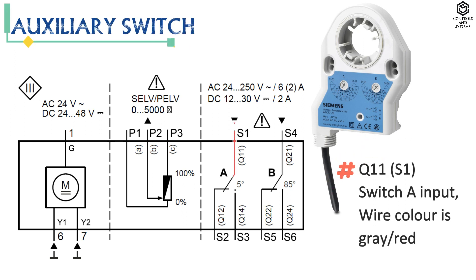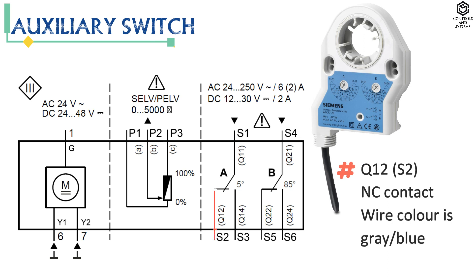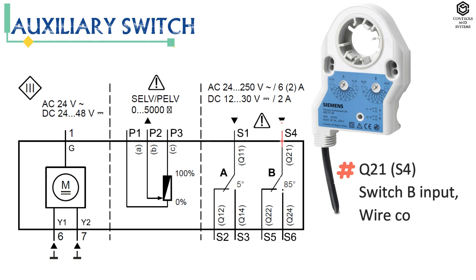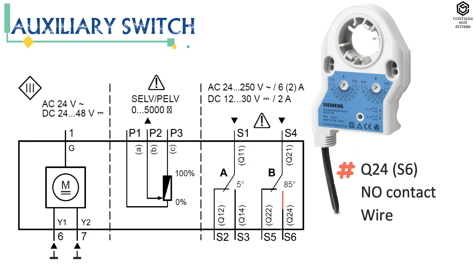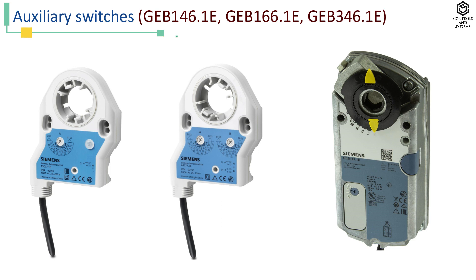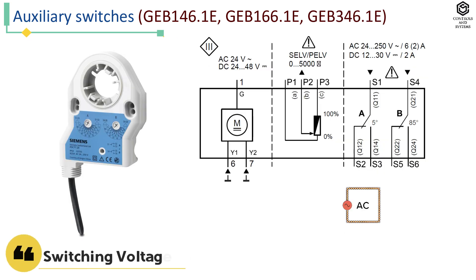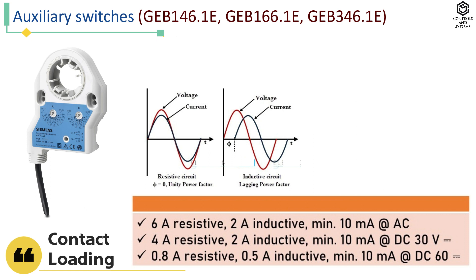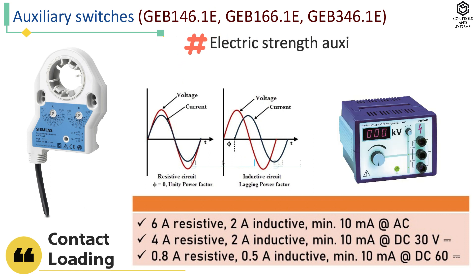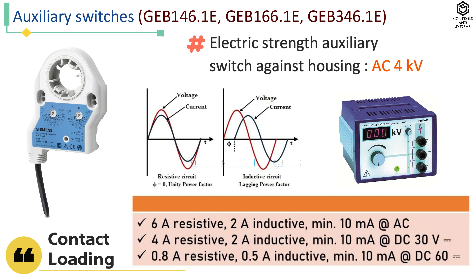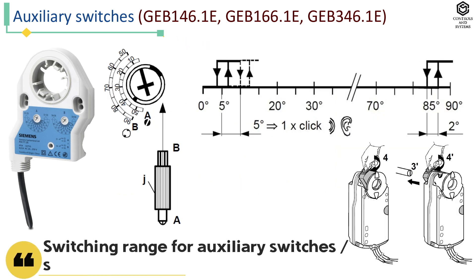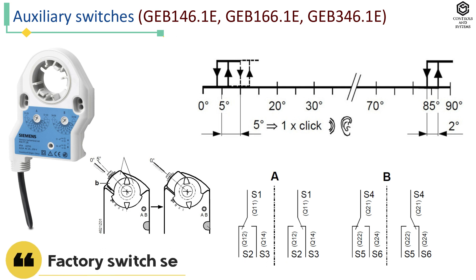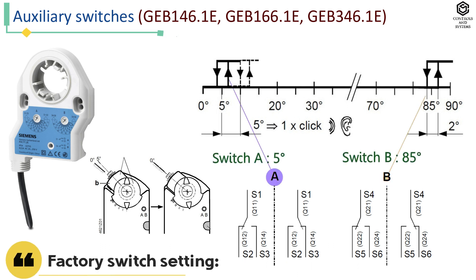Auxiliary switch: Q11 is switch A input, Q12 is NC contact, Q14 is NO contact. Q21 is switch B input, Q22 is NC contact, Q24 is NO contact. Switching voltage is AC 24 to 250 volt or DC 12 to 30 volt. Electric strength of auxiliary switch against housing is AC 4 kilovolts. Switching range is 5 to 90 degrees, setting increments 5 degrees. Factory settings: switch A at 5 degrees, switch B at 85 degrees.